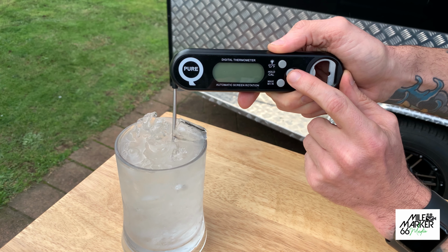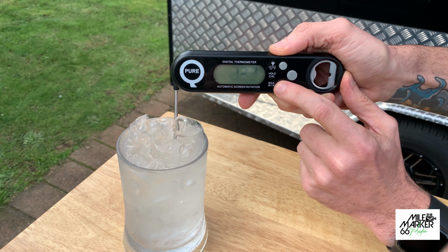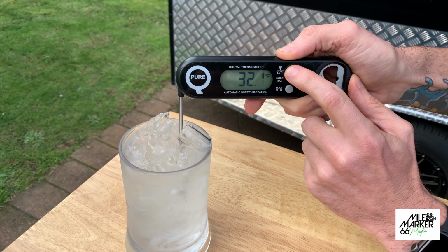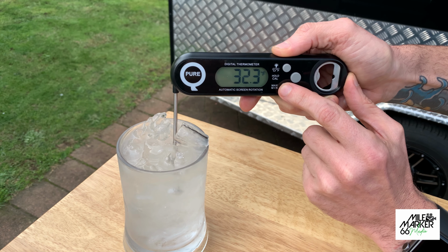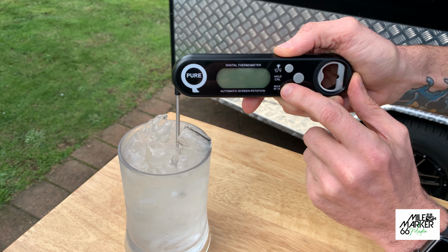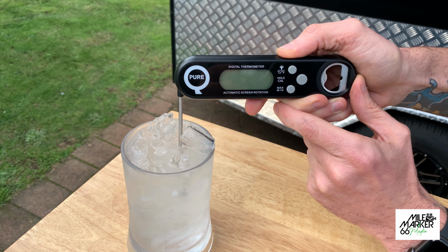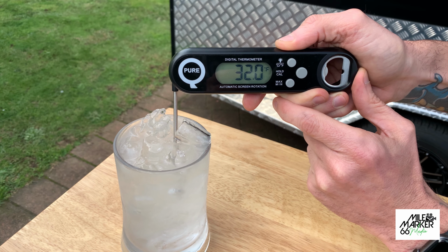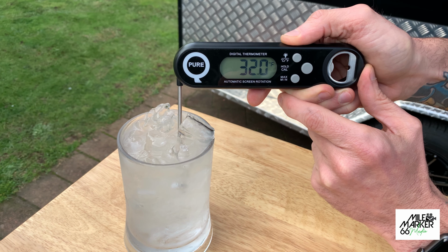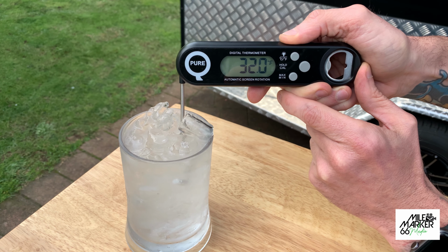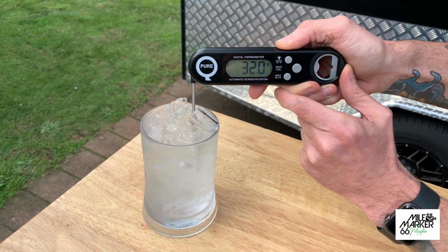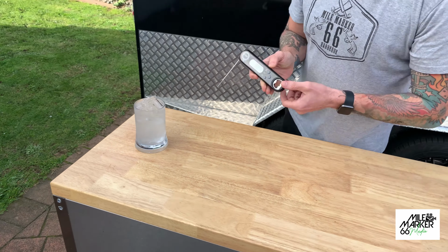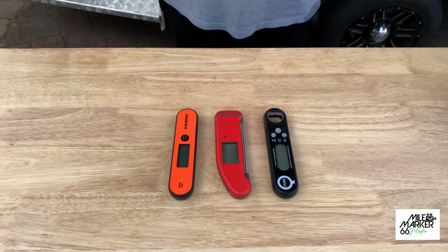With a cal, and then we can use these buttons here to scroll up or scroll down. And I'm going to say 32 degrees is our baseline. That's what we want for 0. I'm going to let that sit there, and now that's calibrated when that stops flashing. So it's as easy as that really, and that is now my baseline, 0 degrees Celsius or 32 degrees Fahrenheit. So there we have it, a review of these 3 instant read thermometers.